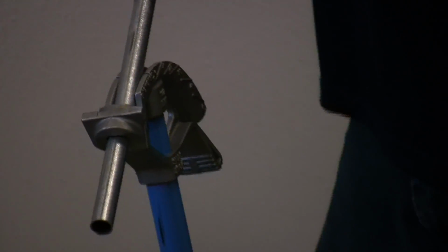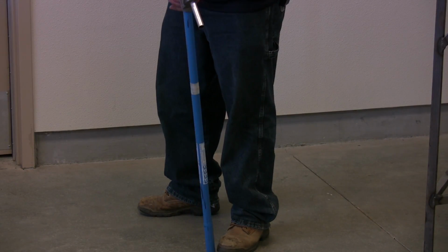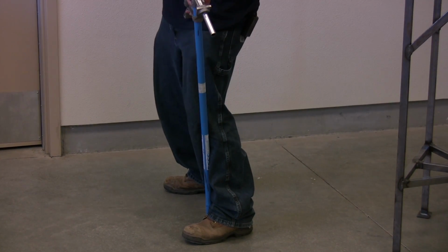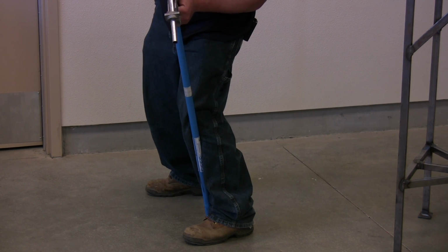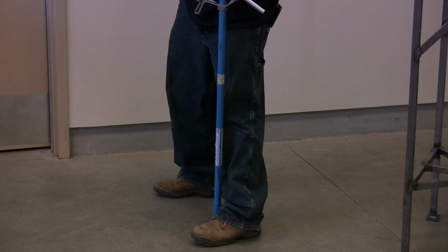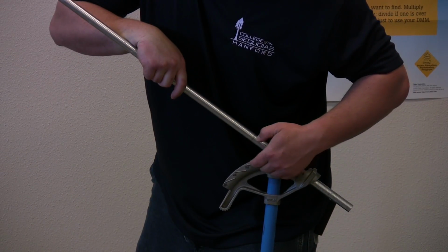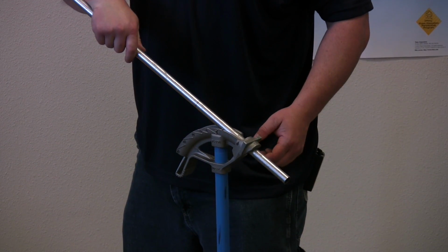As we get closer to bending, one thing you want to be aware of is your footing. You don't want the bender just to be floating around like this, because it can move around or even come up this direction. So what I do is I put my toe in front of it, my knee to the back of it, and then you get in tight so that you could actually bend it. Now when you bend it, the bottom of the conduit is going to line up on the line of the shoe to make sure you have achieved the full 30 degrees. Now let's bend it.